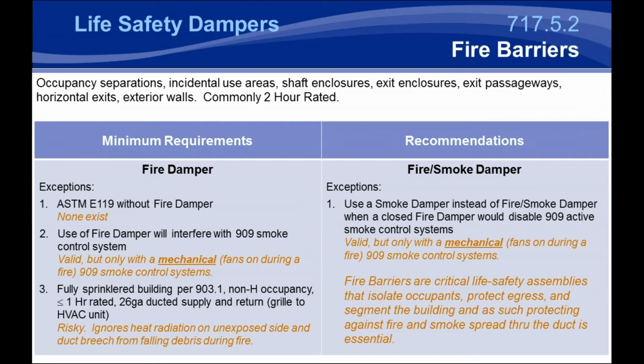All fire dampers are required to go through a duct drop test. So this duct drop test basically has a fire damper installed in some type of wall. Typically the minimum would be a wood truss type wall, and then there's a length of duct connected to it. We'll use a typical breakaway type connection, your Ward Duct Mate, or typical S and drive slip connections. We take that all into account when we actually impact that duct. So the damper's installed in the wall with retaining angles, and a 55-gallon drum with about 400 pounds of sand is dropped on this ductwork.